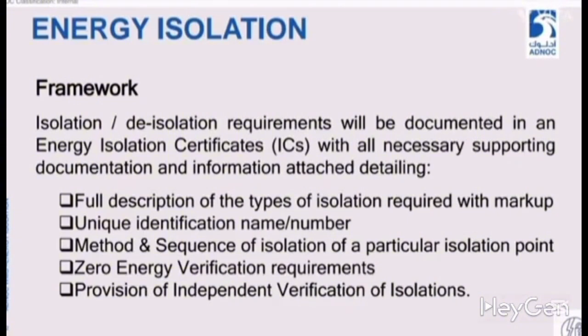What documents can be included? A full description of the type of isolation required with markup. For the equipment or asset we need to work on, the proper type and proper marker of the energy we need to isolate will be mentioned there. Unique identification, name and number for each valve, pipe, instrument and electrical equipment will have a specific number and name. Method and sequence of isolation. We will have the method of how to isolate, blind, how the process is being controlled, whether it is being done electrically or pneumatically. All these things will be clearly mentioned there.